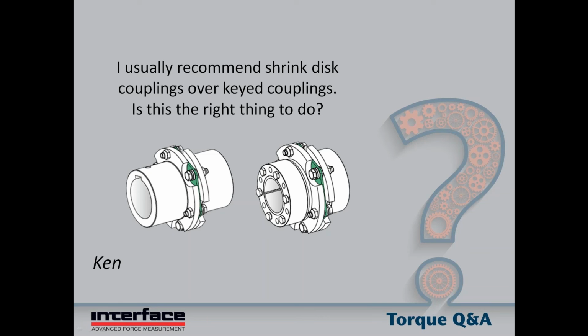And some of the methods that people use in the field that are quite okay with standard shafts and hubs don't necessarily apply when you have a torque sensor in line. You can't put the torque sensor in a press, or you don't want to cool the torque sensor down or heat it up. So you have to be careful to protect the torque sensor from some of the methods that are used to remove keyed hubs. So for all of those reasons we prefer shrink disc couplings. Shrink discs are secure, but when you loosen them up, they'll slide off easily as well.